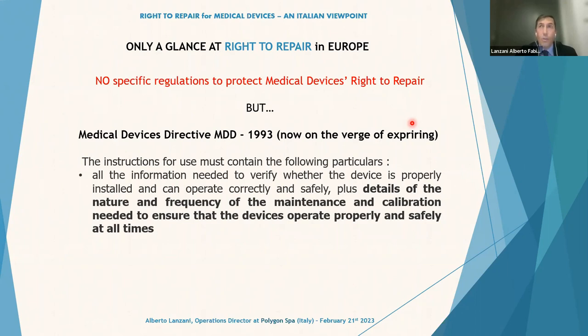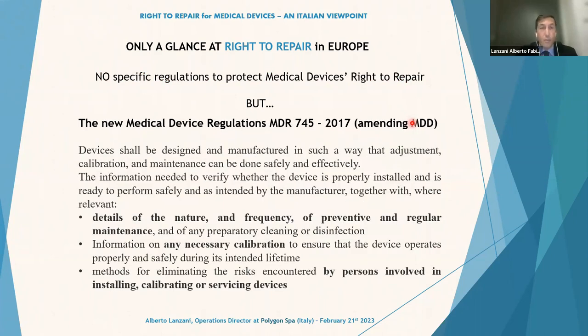The real problem is that no one respects it, even though the law exists. The new regulation, MDR 745, which will amend the previous directive, is even stricter: manufacturers are obliged to give details of the nature and frequency of preventive and regular maintenance. So every time I buy a device, I should receive with it a checklist of preventive maintenance, a service manual, and calibration information to ensure it operates properly and safely, along with methods for eliminating risks encountered not only by users but by people installing, calibrating, and servicing the device.